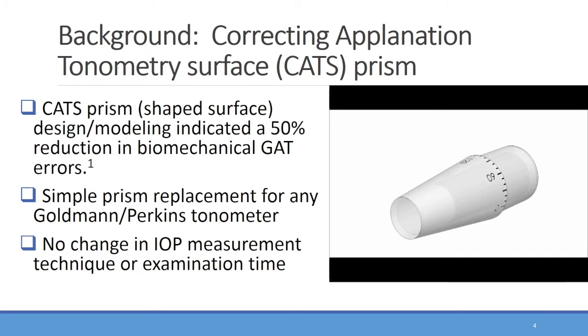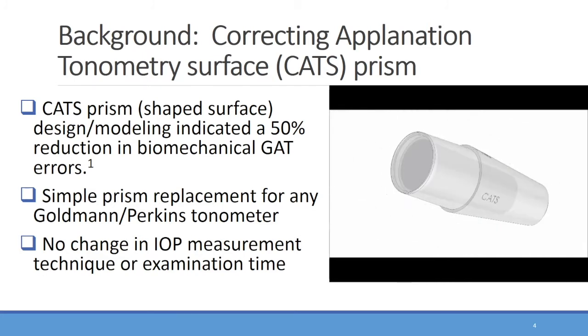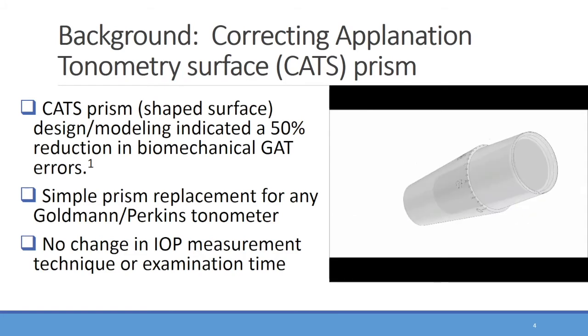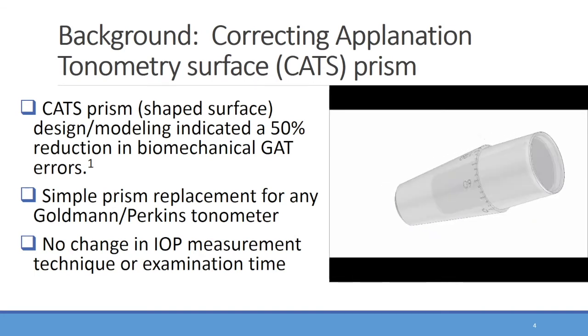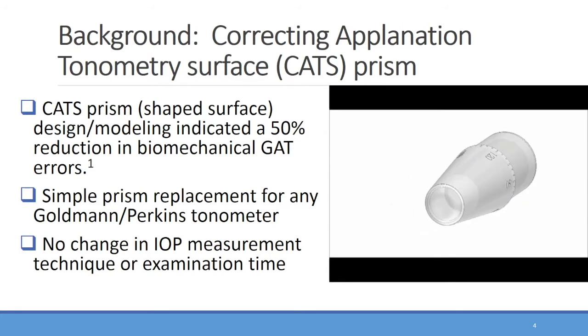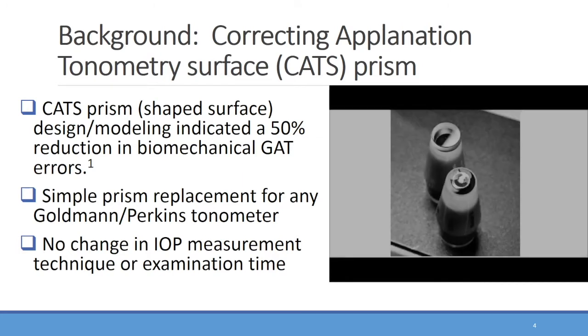The Goldmann prism primarily differs in the contact surface. As shown here, the Goldmann bi-prism has a flat contact with the cornea. The CATS tonometer prism is a replacement prism which fits any of the existing Goldmann or Perkins tonometers without recalibration or alteration in measurement technique or interpretation. The primary difference is the contact surface, which has a central concavity and annular convexity. This photograph demonstrates the difference in applanating surfaces: the flat Goldmann prism surface is in the background, and the CATS prism surface is in the foreground.